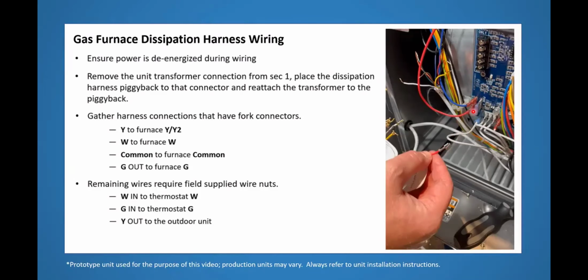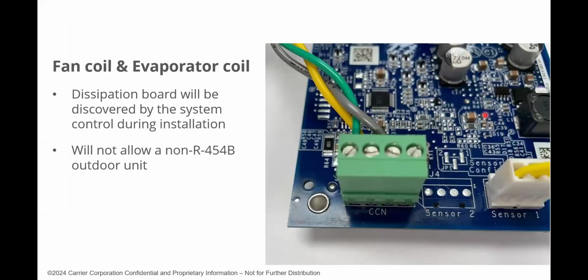They're going to pull the secondary wire for the transformer that goes to the circuit board off, put the piggyback spade there, and plug the transformer back in. That way, this board can get power directly from the transformer. Even if the furnace board takes a dump for some reason, it doesn't work, the alarm board will still be functioning. I don't know why that matters, because if the furnace board's not working, I don't know who's supposed to put the fan on, but at least you'll get the alarm blinking light, right?